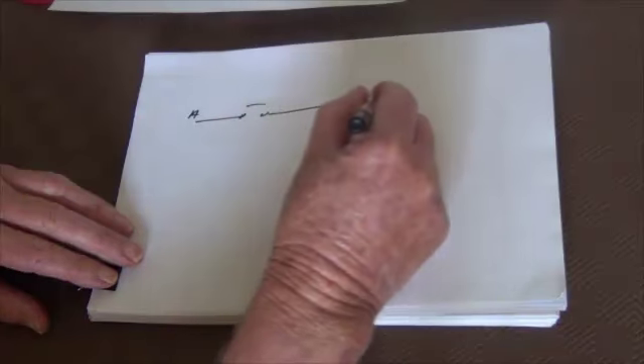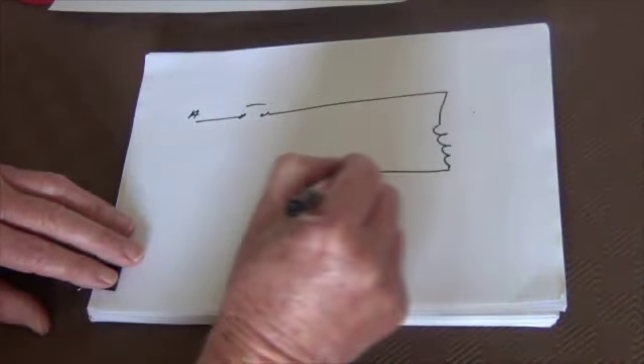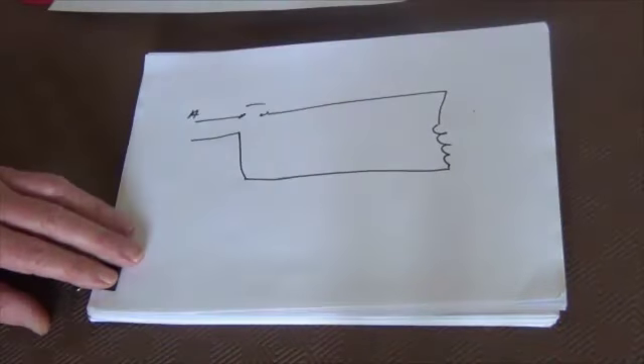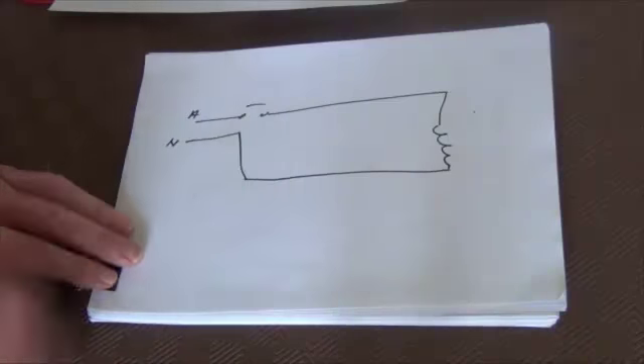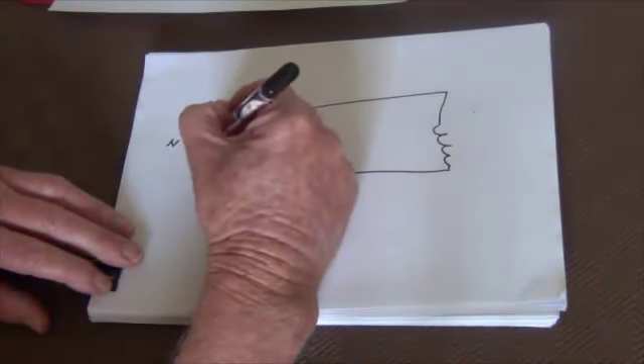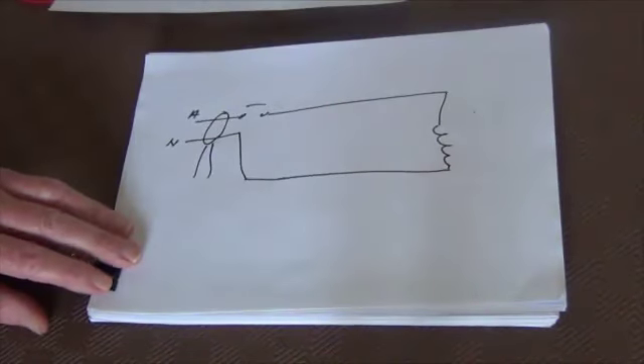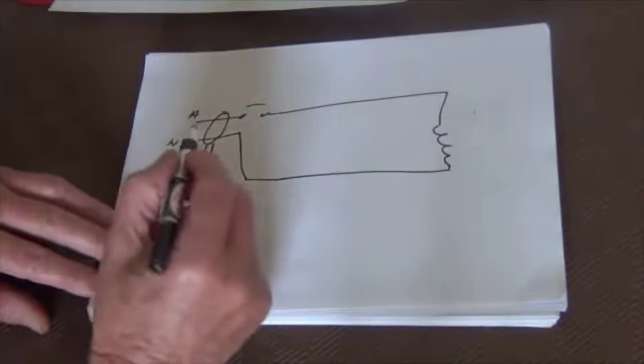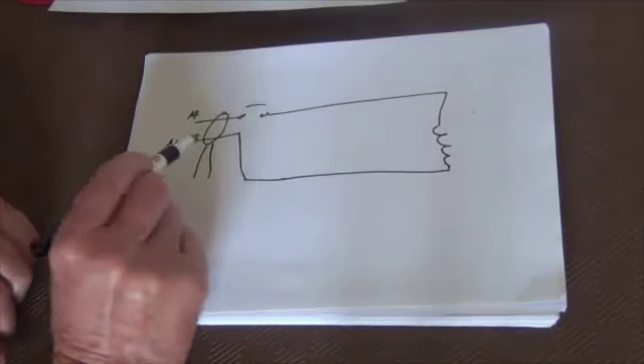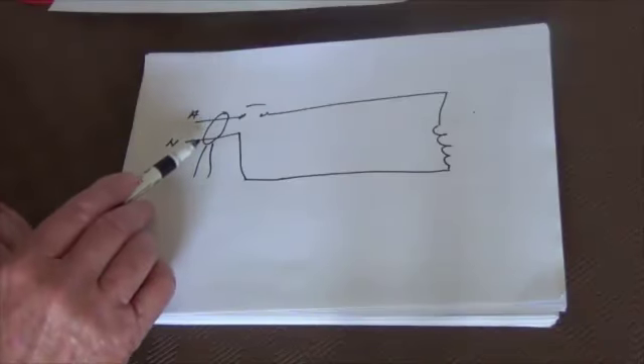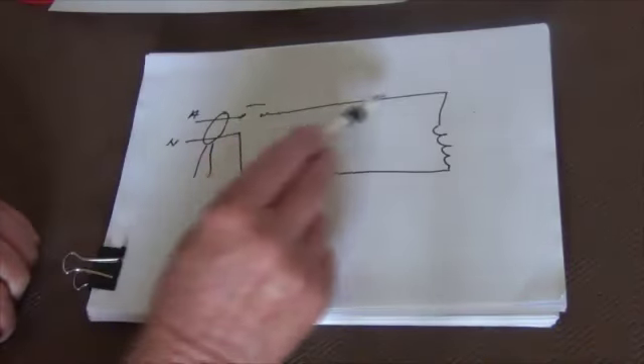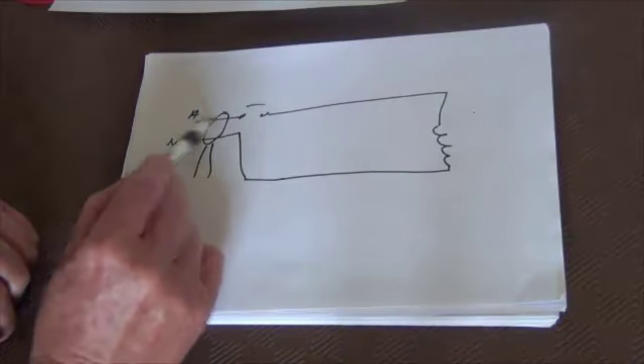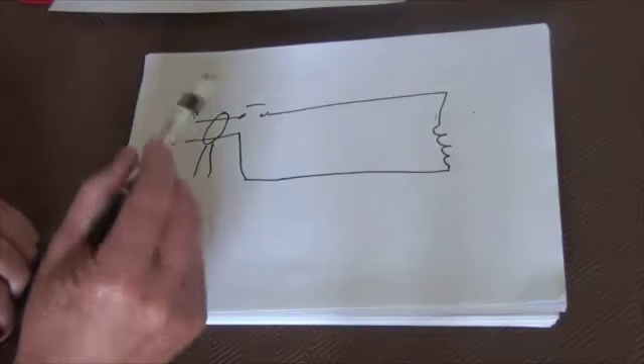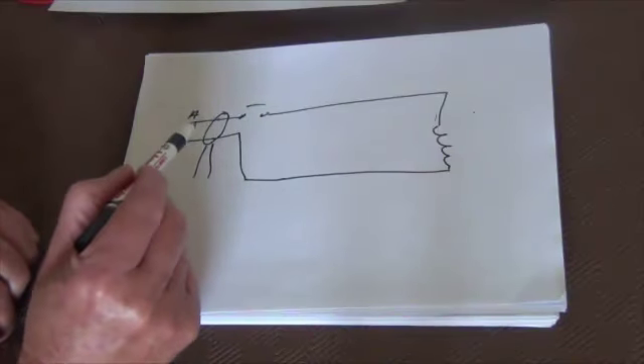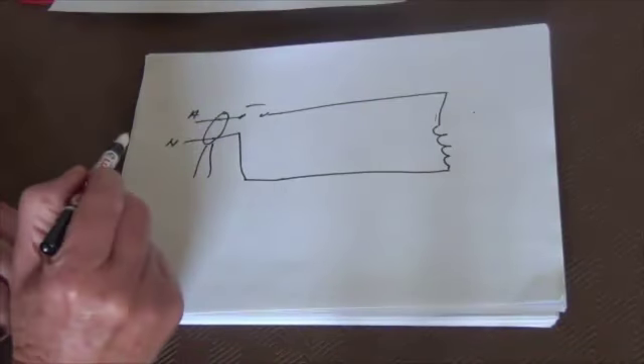Here's your active coming in, goes through the switch, goes through the load, and comes back through the neutral. But we put the neutral together. And around here we put a very tricky device called a current transformer. Now a current transformer is the same as any other transformer, it's just wound slightly differently. And it measures current flowing through here. Now if the current going down there is the same as the current coming back, the two magnetic fields oppose each other and cancel each other out, so there is no magnetic field there.